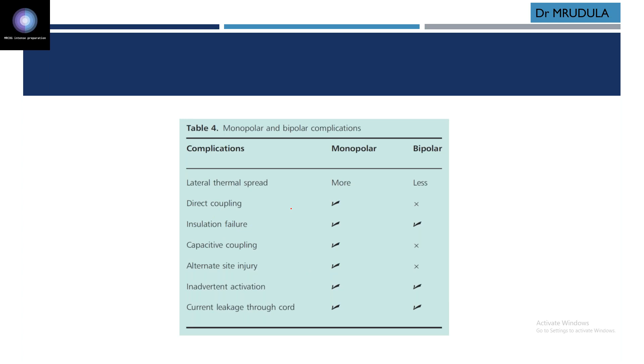Now there is another one called the mushroom effect. So the mushroom effect increases the lateral thermal spread. What happens outside the loop? As the grasped tissue desiccates and coagulates, the current takes the path of least impedance or least resistance outside the jaw of the instrument. So here you can see there will be thrombus formation, and increased impedance. So now what will happen? Current flows away from this instrument, away from this compressed tissue, and it takes the path of least resistance, and it can result in collateral thermal energy injury to nearby structures. So nearby structures around the area where you have grasped this tissue will get affected. Here you can see you have grasped this tissue in between two electrodes. Along with this, another tissue is also affected because of this lateral or collateral thermal spread. It is called the mushrooming effect.